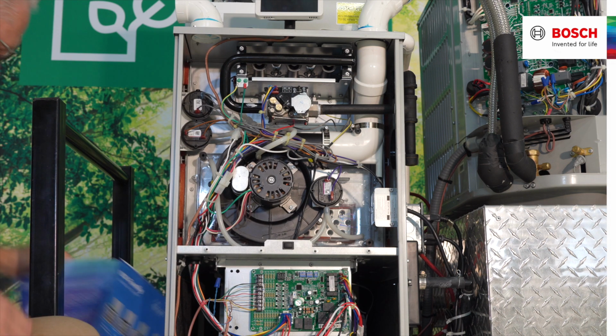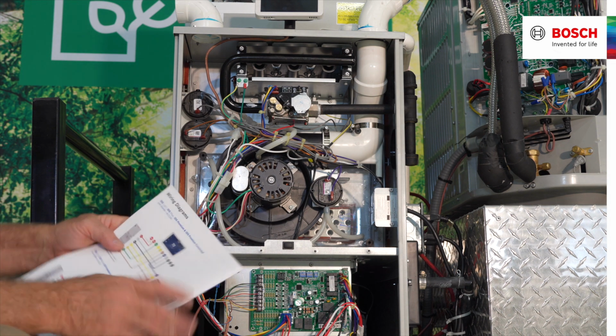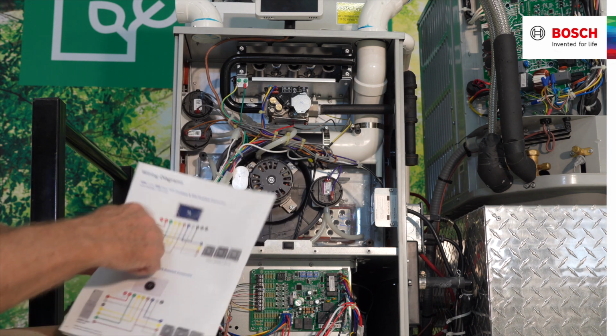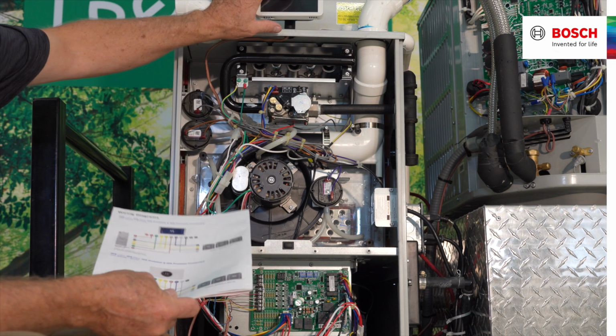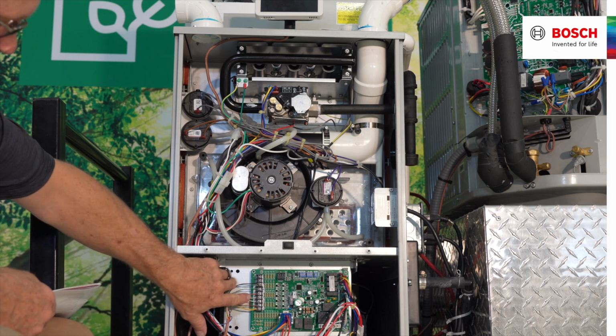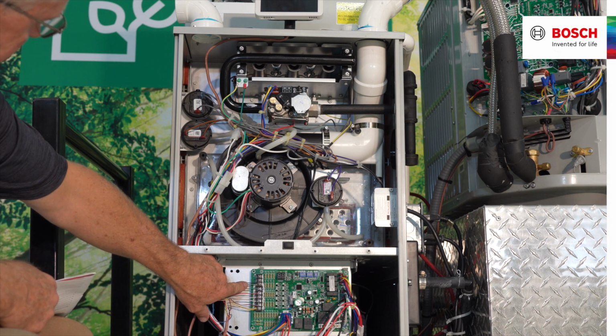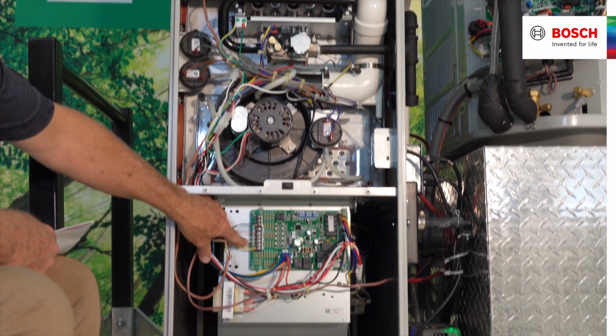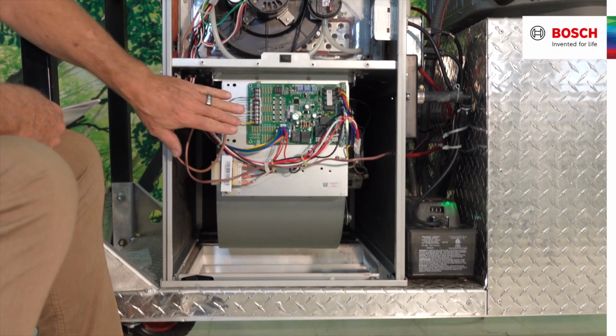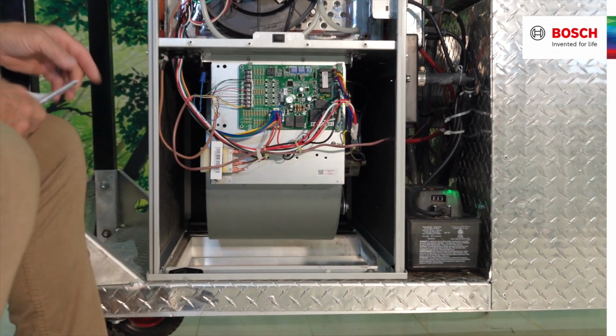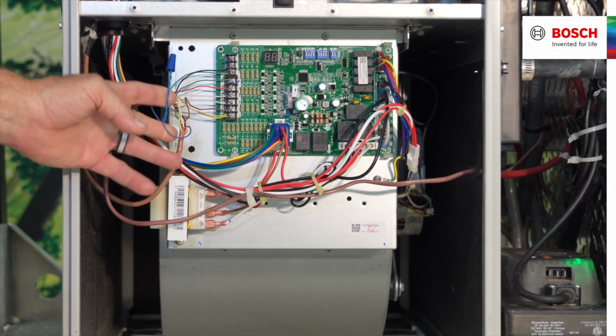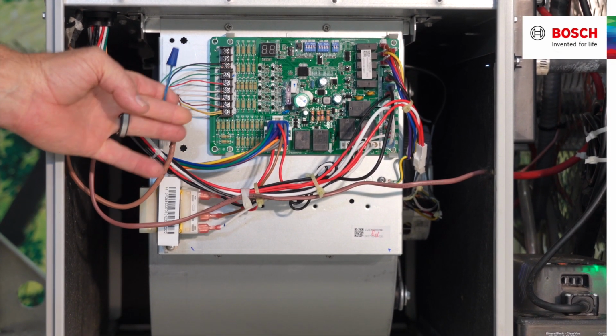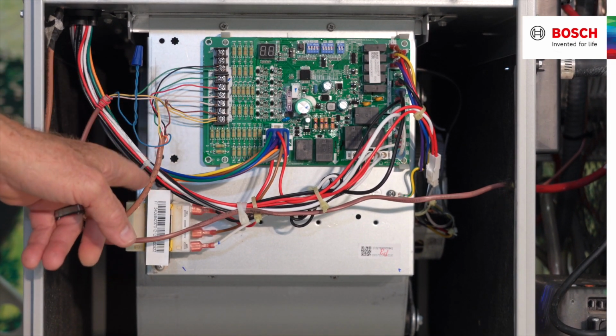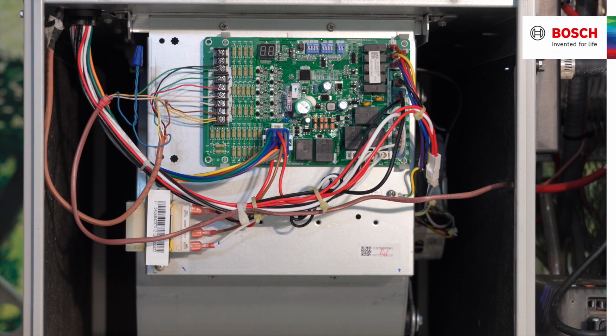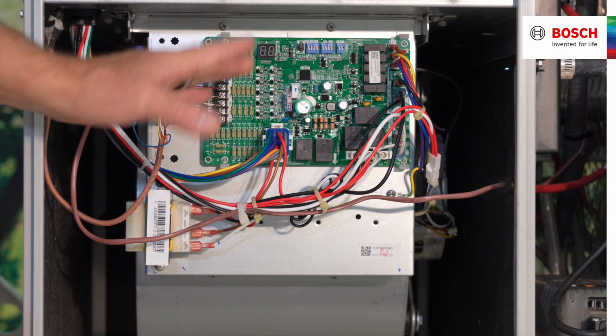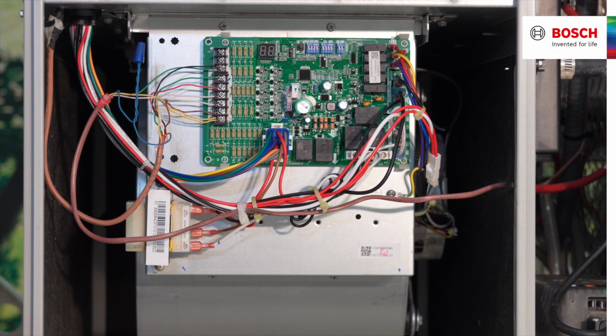Other thing that I want to look at is in the quick start guide. We have, of course, all of the wiring diagrams that you're going to need for the condensing unit, the BCC 100, and then the gas furnace. Connection places are here. We can see that we have a common, a green, a red, W2, W1, Y1, Y2, but we don't have any place for the B wire. And you notice that in this particular application, the B wire is actually coming from the thermostat, wire nutting here in the control compartment, taking and making a complete circuit all the way back out to the reversing valve in the condensing unit. So there is not a B terminal on the board itself. It is just done with a wire nut connection.